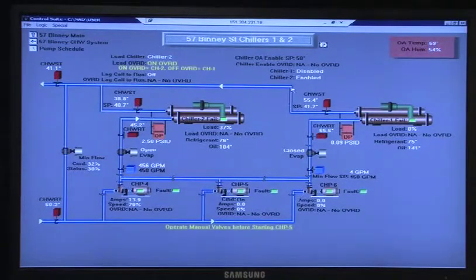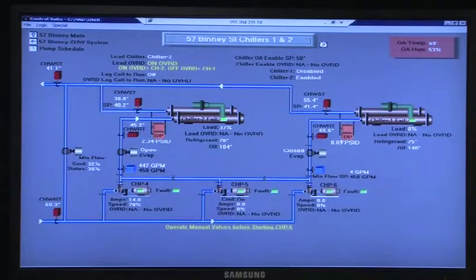And that load override underneath that? Right now, chiller one, this right here, it says load override. Let me see where it's coming from. Can you right click that real quick? You might be able to override the load of the chiller to get a second chiller to come on. I might have had redundancy-type points in there. Charlie might have asked for it when he was doing commissioning. Sometimes he wanted to be able to simulate things.